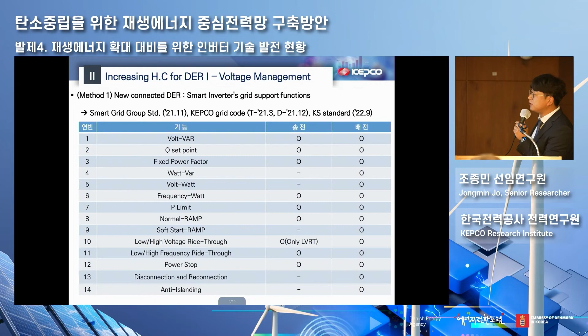Second, I'm talking about existing inverters — their voltage should also be managed. For that, we are using a monitoring control device, and smart inverter functions can be used based on autonomous functions. Existing inverters do not have smart functions, so we can build control and monitoring functions so the inverters can be embedded with grid control, allowing them to function as smart inverters.